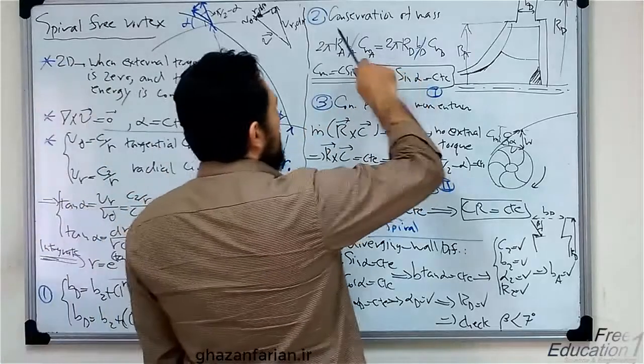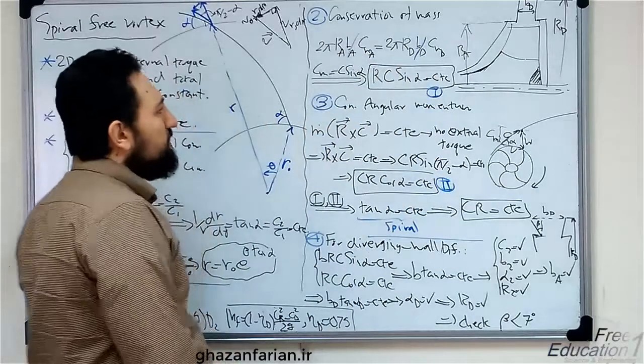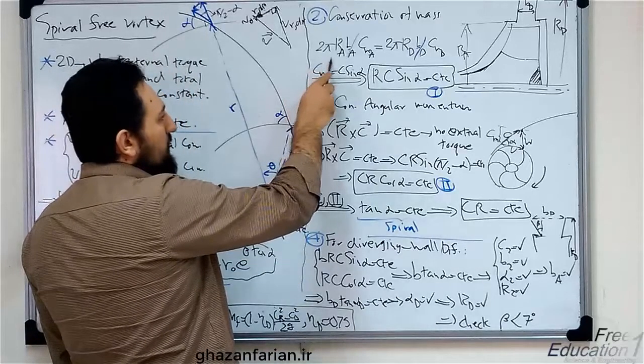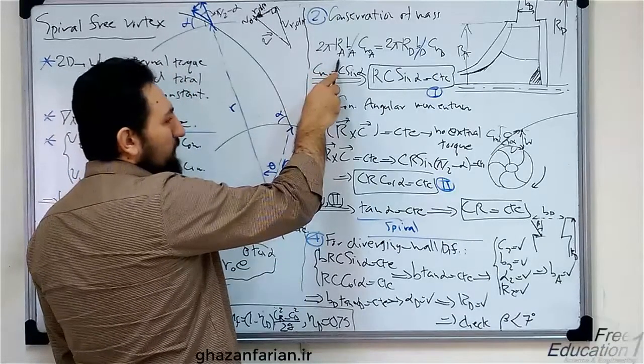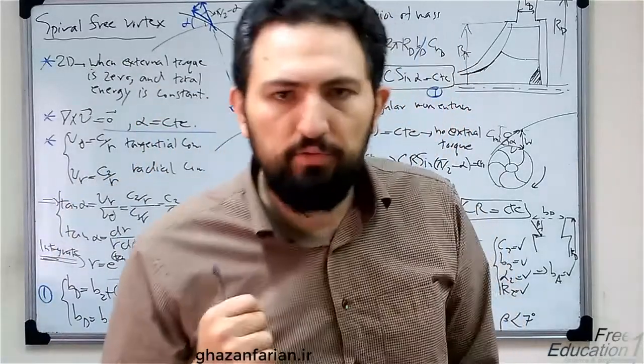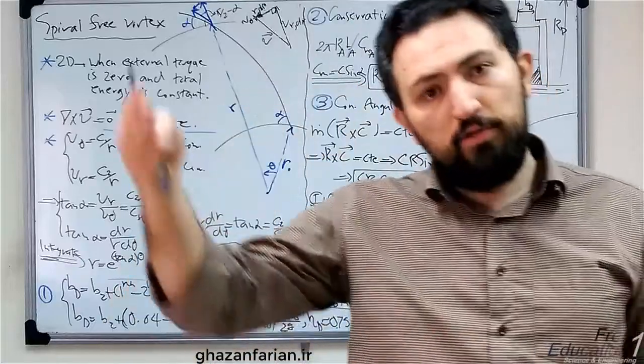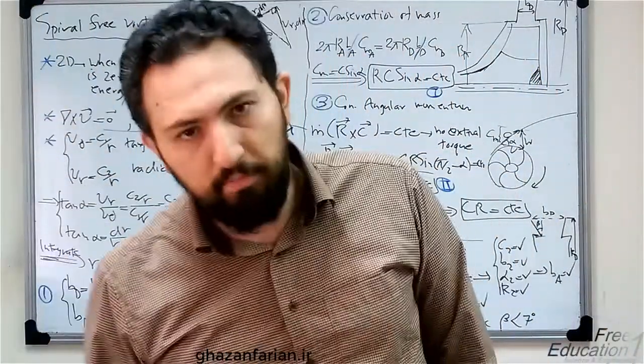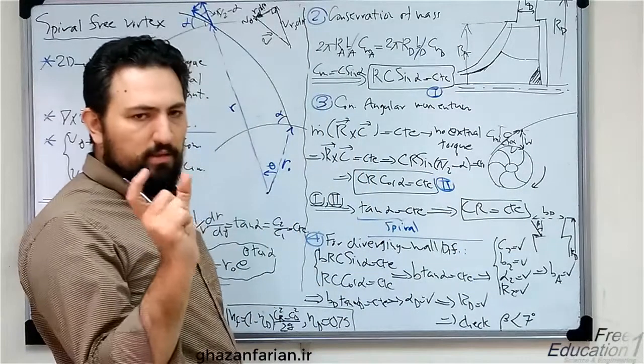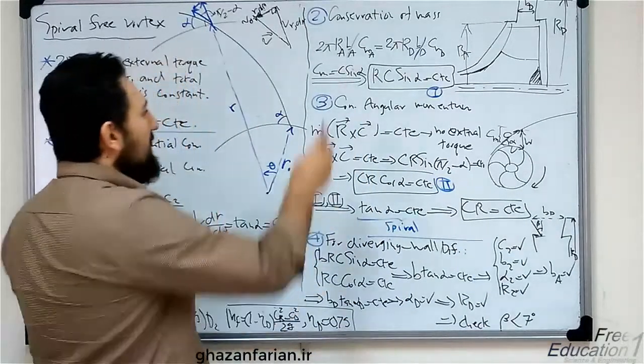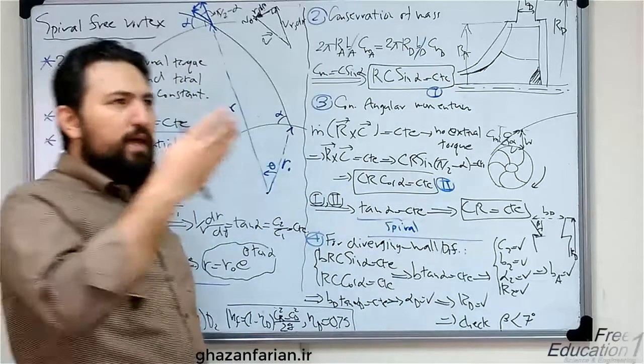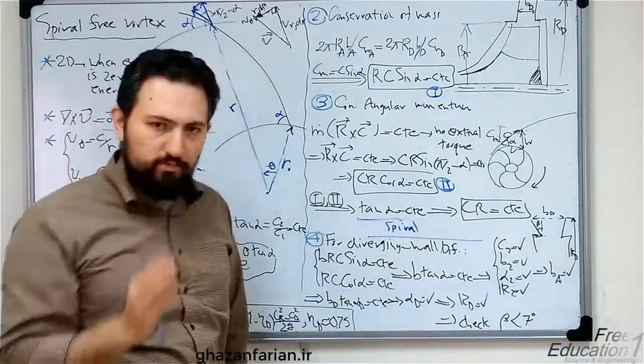Start from the conservation of mass. The flow rate is 2π times R sub A, where R sub A is the radius of the input of the diffuser, which equals the radius of the output of the impeller. B sub A is the width of the diffuser at the inlet, and C sub MA is the component of the absolute velocity along the radial direction.